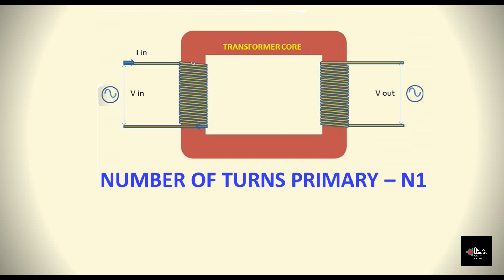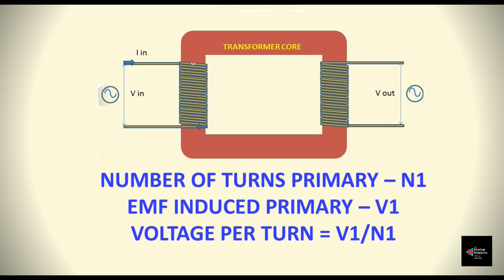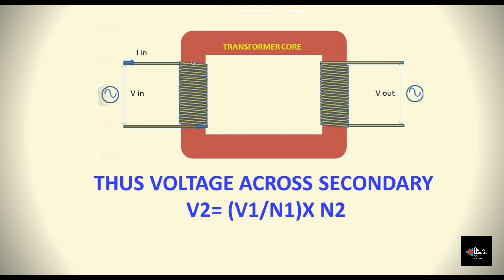Now if this primary winding has N1 number of turns, and the supply voltage or induced voltage across the primary winding is V1, the voltage per turn in the primary winding is V1 by N1. So exactly this V1 by N1 voltage will appear across each turn of the second winding. If the second winding has N2 number of turns, then the total voltage across the second winding is N2 multiplied by V1, the whole divided by N1. Let us say this is V2.